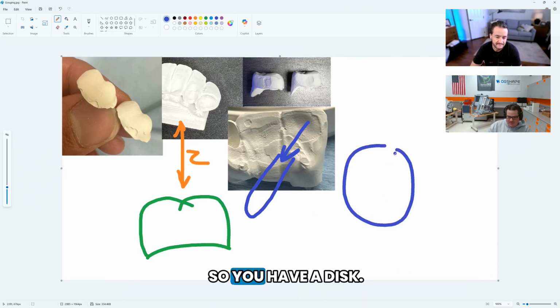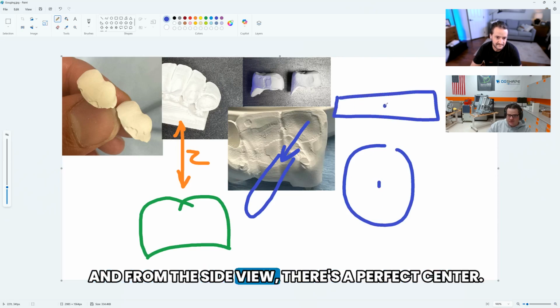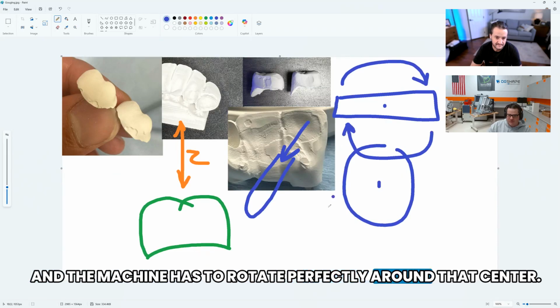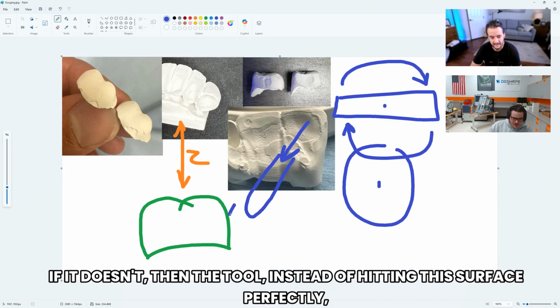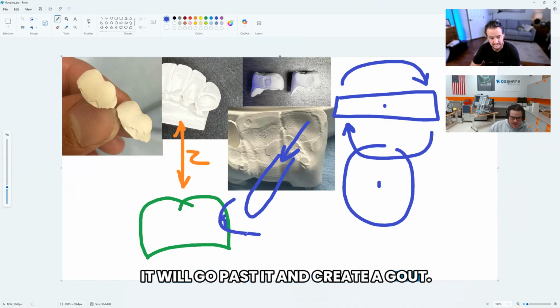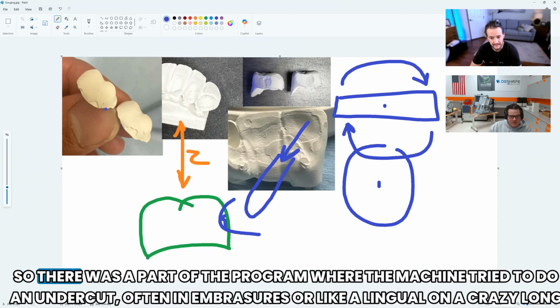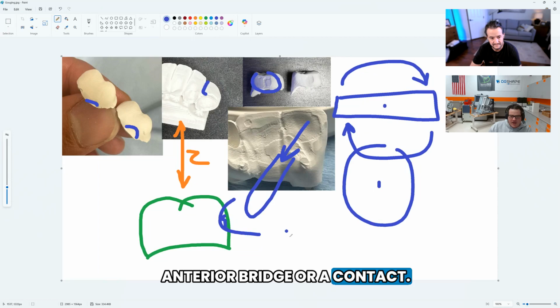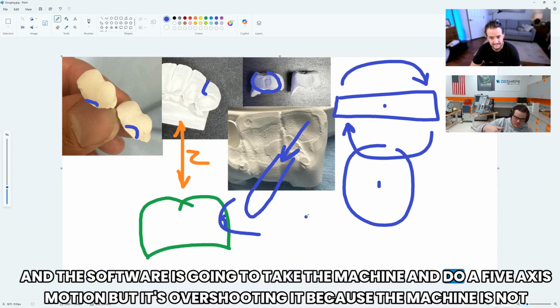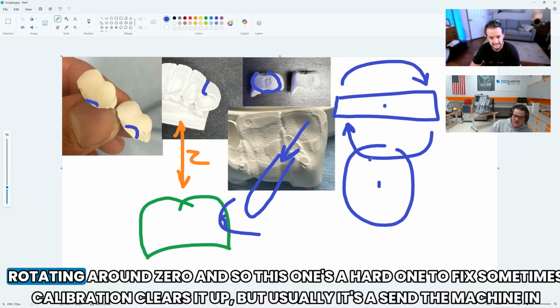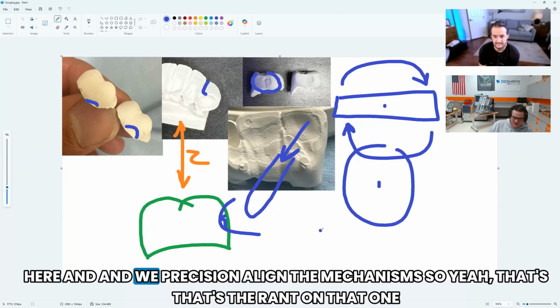So you have a disc. It's got a perfect center from this way, and from the side view, there's a perfect center. And the machine has to rotate perfectly around that center. If it doesn't, then the tool, instead of hitting this surface perfectly, will go past it and create a gouge. And so every one of these is actually from undercut machining. There was a part of the program where the machine tried to do an undercut, often in embrasures, or like a lingual on a crazy long anterior bridge, or a contact. There are undercuts, and the software is going to take the machine and do a 5-axis motion, but it's overshooting because the machine is not rotating around 0. And so this one's a hard one to fix. Sometimes calibration clears it up, but usually it's send the machine in here and we precision align the mechanisms. So yeah, that's the rant on that one.